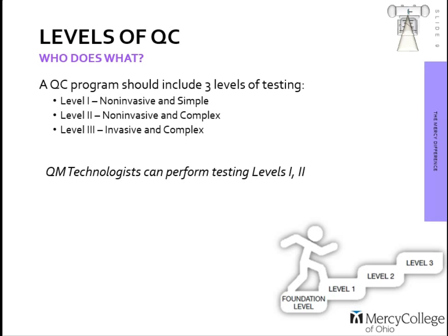Level 3 should be done by a medical physicist, and it has to do with acceptance testing, making sure that any new piece of equipment is tested before it's ever used on a person. Every time there's a repair done on a piece of equipment, quality control is performed, making sure it's up to the levels you would expect and in line with where it was before. Any error correction testing or routine performance evaluations, at specific intervals, whether 6 months or a year, should be done by a medical physicist. But nonetheless, the QM tech can do some QC-based procedures.